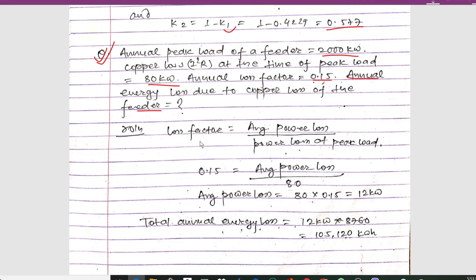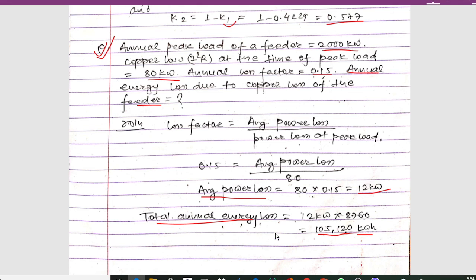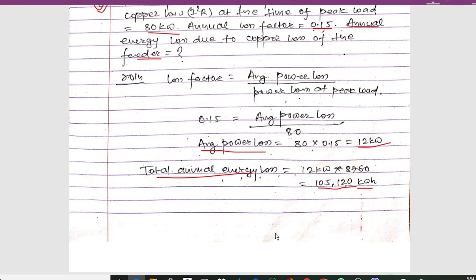The loss factor is 0.15, and the power loss at peak load is 80 kilowatt. From this relation, we can obtain the average power loss as 12 kilowatt. To calculate total energy loss, we multiply the average power loss by 8760 hours, giving us 105,120 kilowatt-hour. This is our final answer.